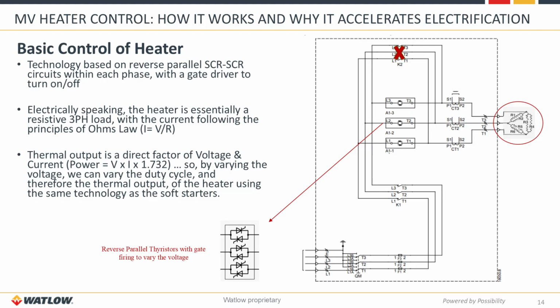So by varying the voltage, we can also then vary the duty cycle or the power output to the unit using the same technology as the soft starters within the business. So the diagram down here just shows you how that works. You've got these reverse parallel thyristors with a gate control on them. By firing that gate at a certain position within the sinusoidal wave, we can turn on and off those sinusoidal waves at any frequency that we would like to. And by doing so, we can vary that voltage or the effective voltage that gets out to the heater itself.